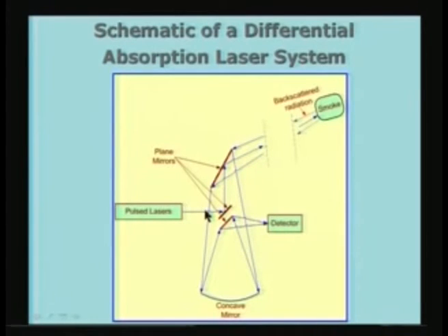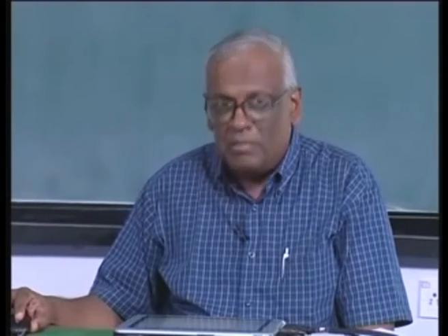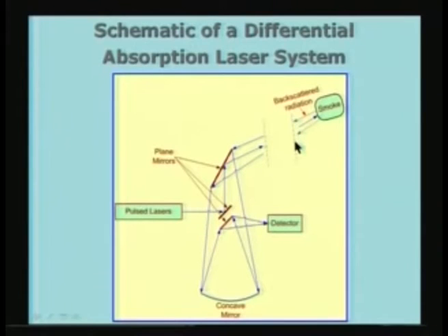The pulse duration and the duration between pulses are under my control, and also the duration over which I can make the measurement is in my control. So, I can choose a certain window in between two pulses such that I can sample this particular region, for example. Of course, this region can be shifted, and accordingly we have to shift the duration over which we are going to make the measurement.